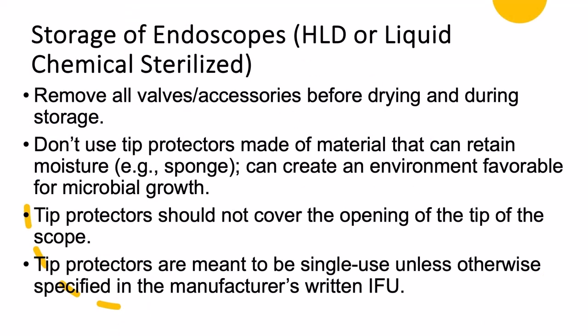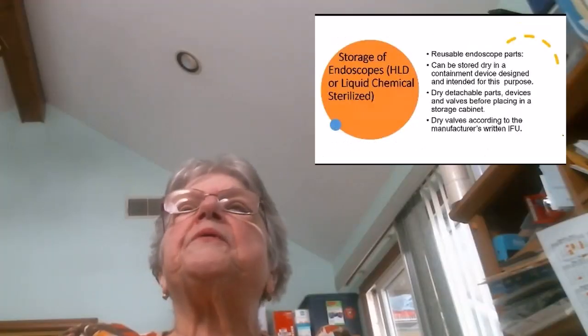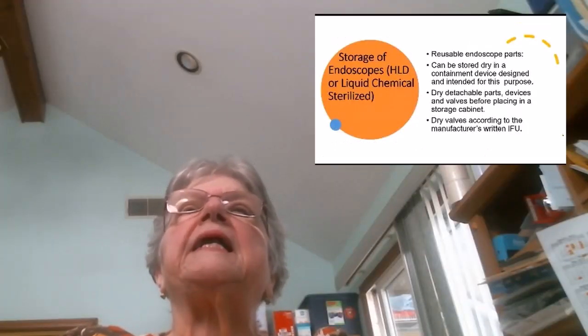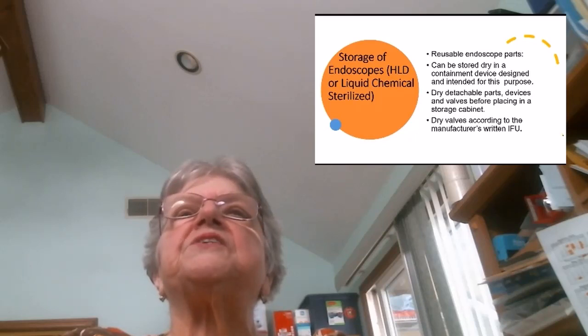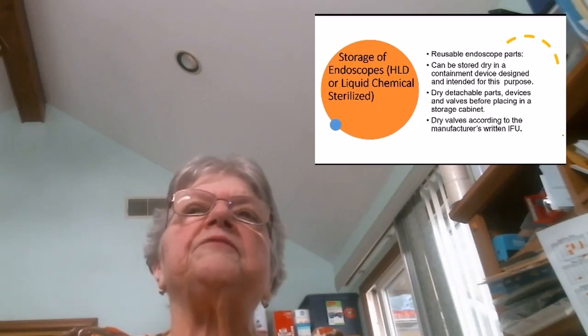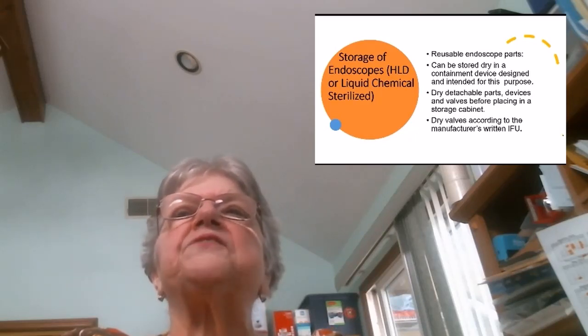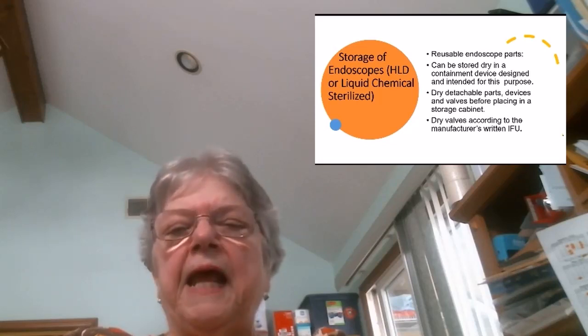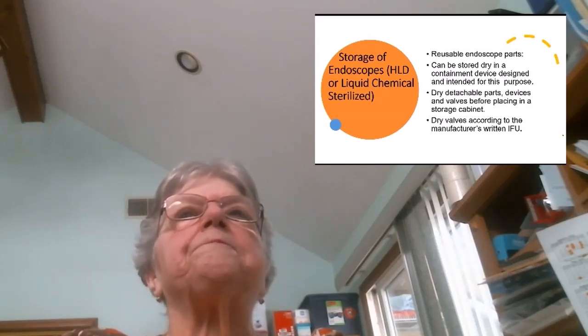Don't use tip protectors made of a material that can retain moisture, such as the sponge tip protectors, because this can create an environment favorable for microbial growth. Your tip protectors should not cover the opening of the tip of the scope, and tip protectors are meant to be single-use unless otherwise specified in the IFU. For reusable endoscope parts, these can be stored dry in a containment device designed and intended for this purpose. You should dry all of your detachable parts and devices and valves before they're placed in the storage cabinet, and they're dried according to the IFU.